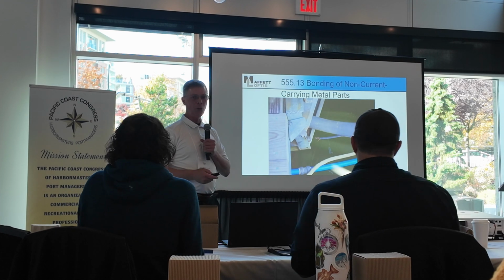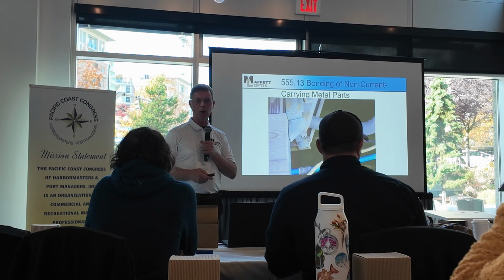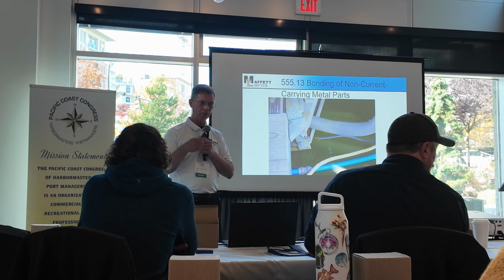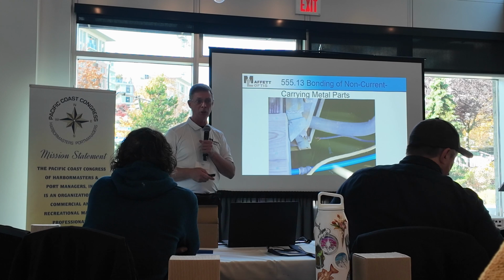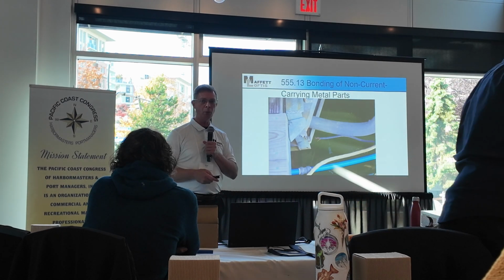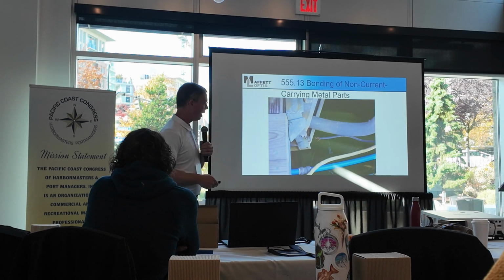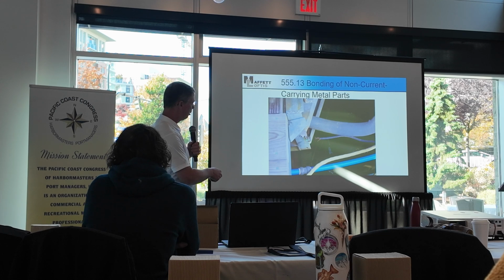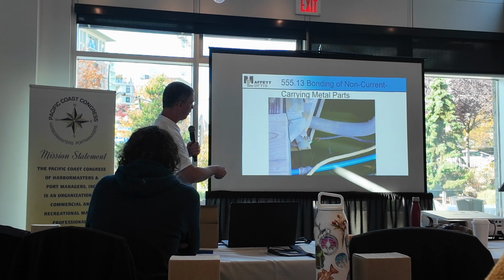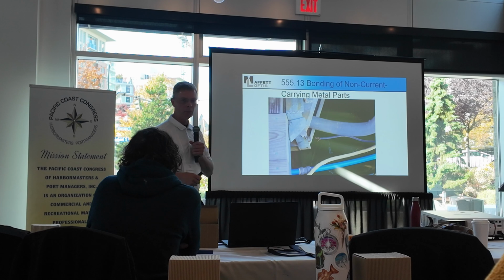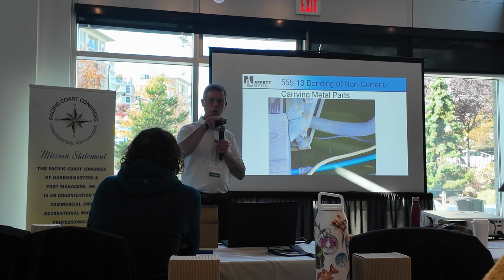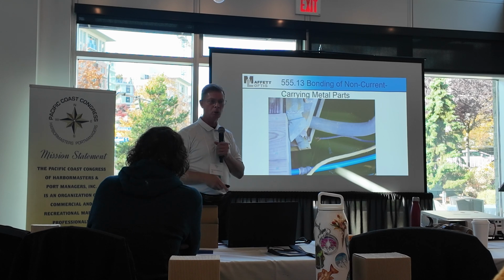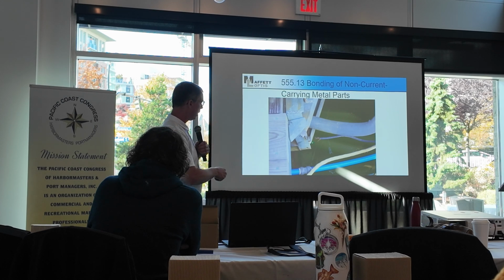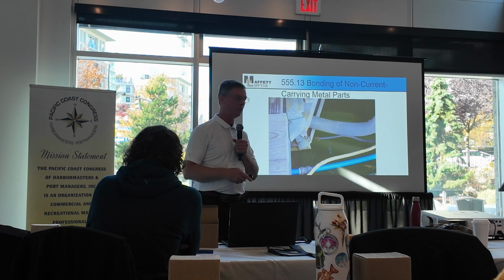So look, if you don't have those bonded now for metal gangways, they need to be bonded, especially if you have electrical cables running out. So see if they're bonded or not. If they are, make sure it's intact, make sure it's tight. And I don't like this type of bonding lug, because if this is moving back and forth, that will tend to want to rotate. My plans always have two bolts in the lug, so it won't rotate and come loose. So I would highly recommend replacing that with a two-hole lug, and then make sure that's bonded.